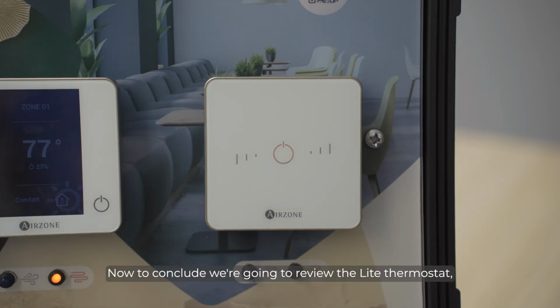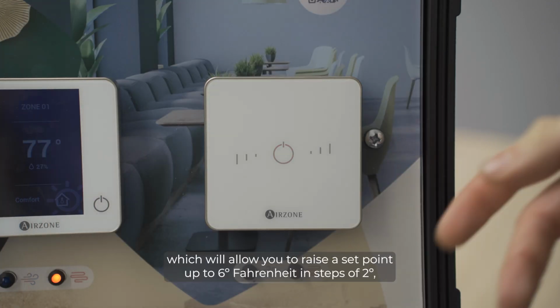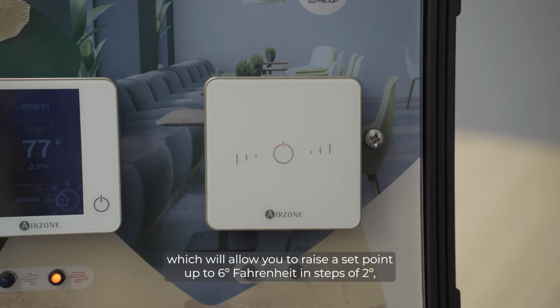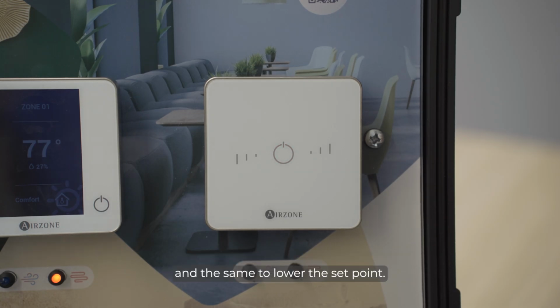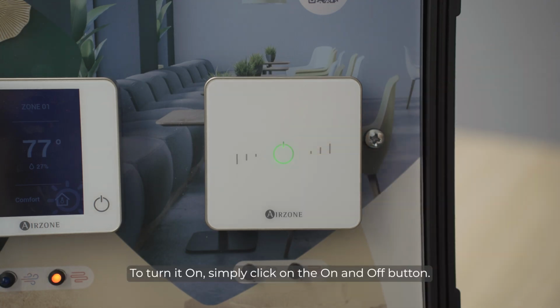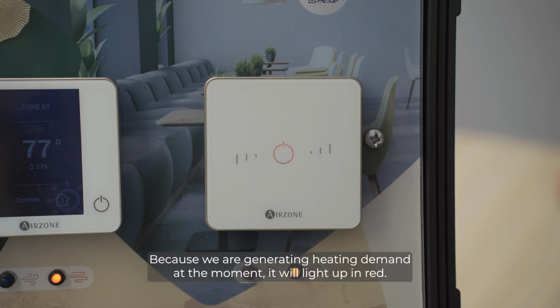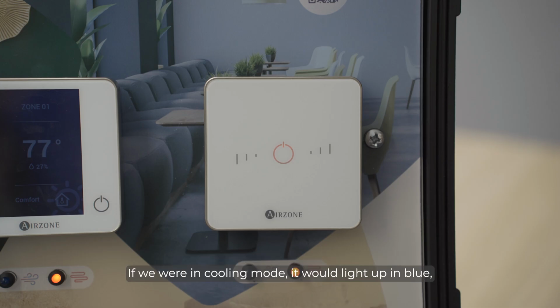Now to conclude, we're going to review the Lite thermostat, which will allow you to raise the set point up to 6 degrees Fahrenheit in steps of 2 degrees, and the same to lower the set point. To turn it on, simply click on the on and off button. Because we are generating heating demand at the moment, it will light up in red. If we were in cooling mode, it will light up in blue. And if we were in comfort mode, the LED will show green.